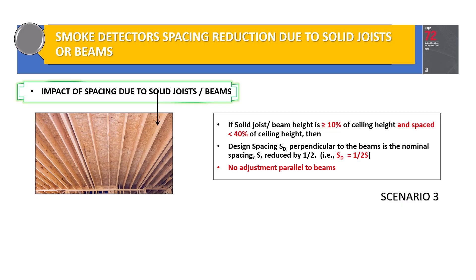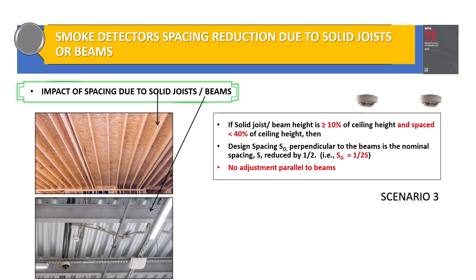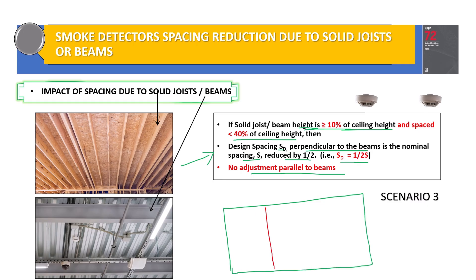In Scenario 3, if you have solid joists or beams and the depth of the beam or solid joist is greater than or equal to 10 percent of the ceiling height, and the beams or joists are spaced less than 40 percent of the ceiling height, then the design spacing perpendicular to the beam is the nominal spacing reduced by half — SD equals half S — with no adjustment parallel to the beams.